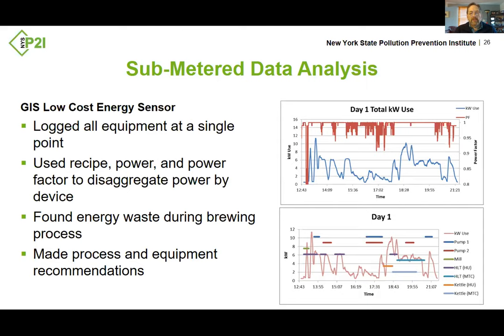So you can see on the bottom chart, we were able to overlay what was running at all of these times. And then we were able to characterize the equipment so that we could look at any day's worth of data or their other brewing lines, and we would understand which pumps were running, which heaters were heating.